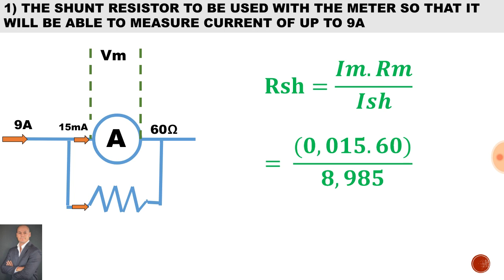I_m is 0.015 A and the resistance of the meter is 60 ohms. I shunt gives us 8.985 amps flowing through the shunt winding and the remaining current flowing through the meter. Therefore the value of the shunt resistor is 0.1 ohms.